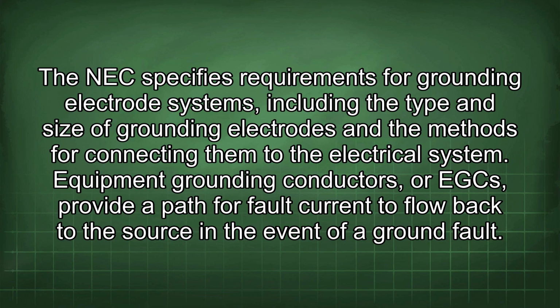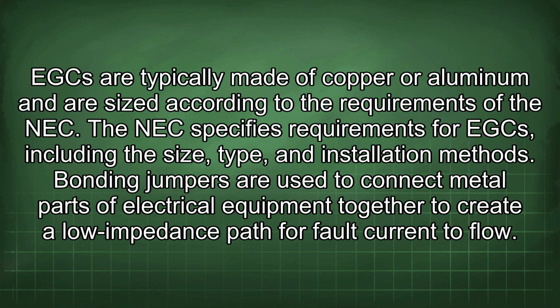Equipment grounding conductors, or EGCs, provide a path for fault current to flow back to the source in the event of a ground fault. EGCs are typically made of copper or aluminum and are sized according to the requirements of the NEC. The NEC specifies requirements for EGCs, including the size, type, and installation methods.